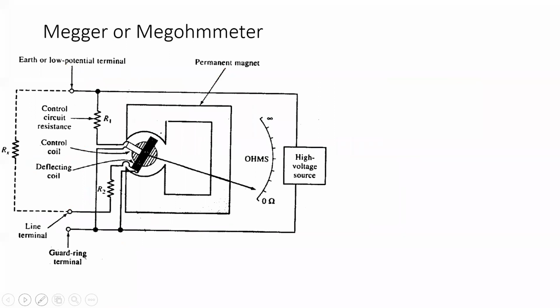Now, lastly, today, let me discuss something about the mega ohm meter, which is also known as the Megger. This meter is used for measuring high resistance, or any form of resistance actually, but normally it is used for determining cable faults or measuring high resistance. The advantage of this device compared to other methods is that it is calibrated in terms of resistance, so you don't have to use separate voltmeters or ammeters. If you connect the resistance across the two terminals of this instrument, you can take the reading directly in ohms.